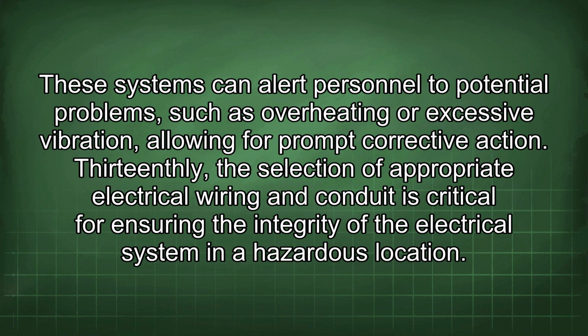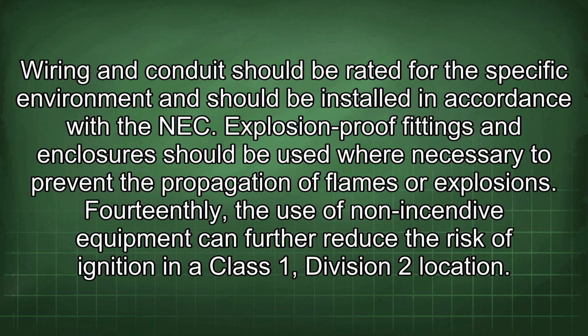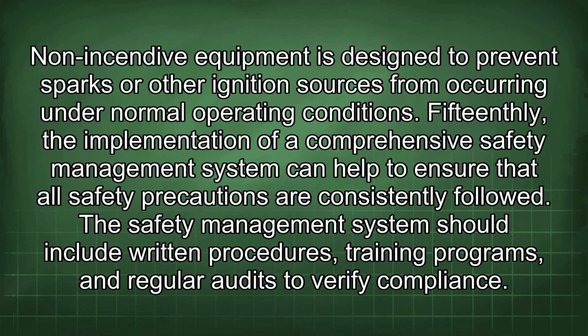13thly, the selection of appropriate electrical wiring and conduit is critical for ensuring the integrity of the electrical system in a hazardous location. Wiring and conduit should be rated for the specific environment and should be installed in accordance with the NEC. Explosion-proof fittings and enclosures should be used where necessary to prevent the propagation of flames or explosions. 14thly, the use of non-incendive equipment can further reduce the risk of ignition in a Class 1 Division 2 location. Non-incendive equipment is designed to prevent sparks or other ignition sources from occurring under normal operating conditions.